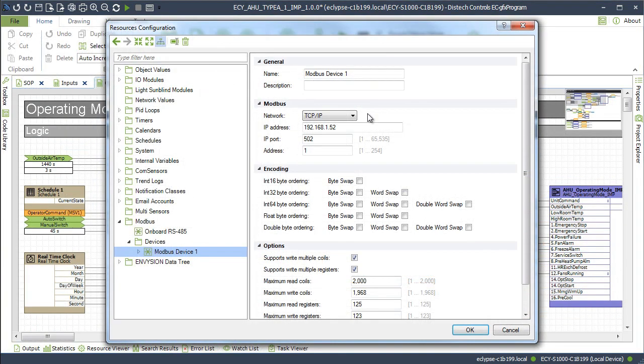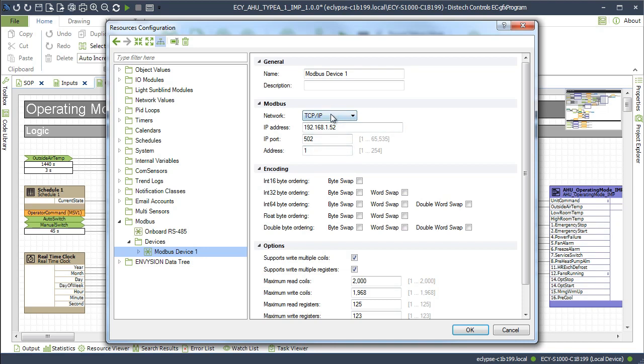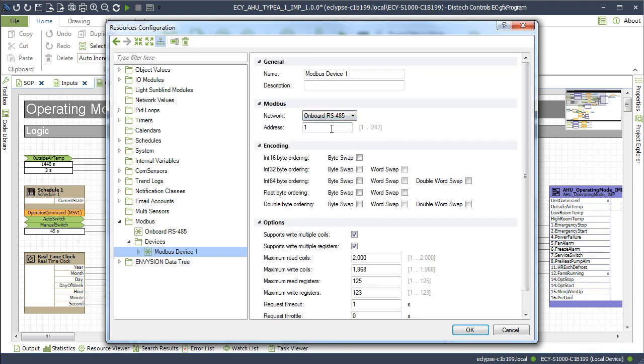In the resource configuration, configure the Modbus device. These are the Modbus device TCP IP configuration parameters. Or select the onboard RS-485 option for the Modbus RTU devices connected to the controller's RS-485 port. The byte ordering and options can be set for each Modbus device. Data types as large as 64 bits are supported.